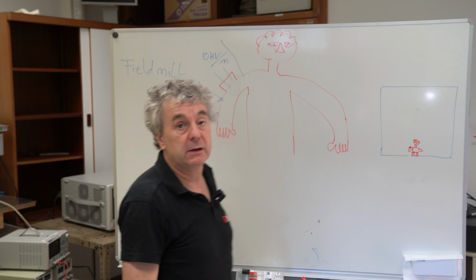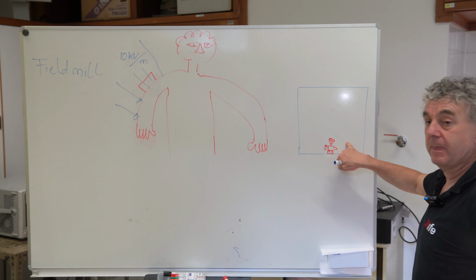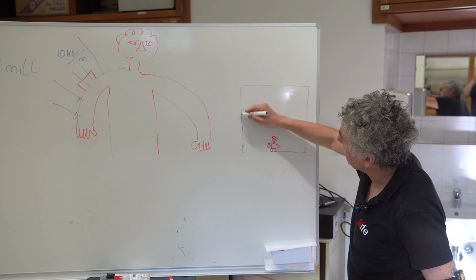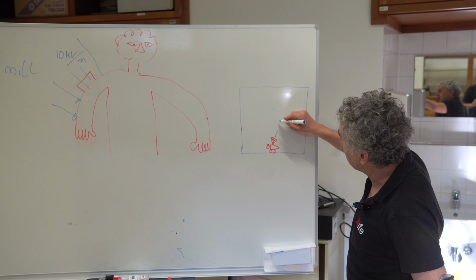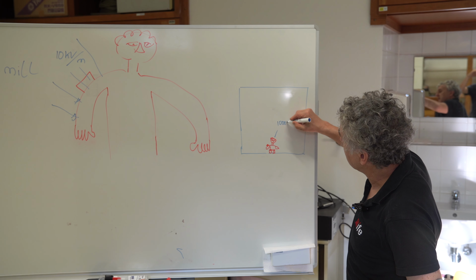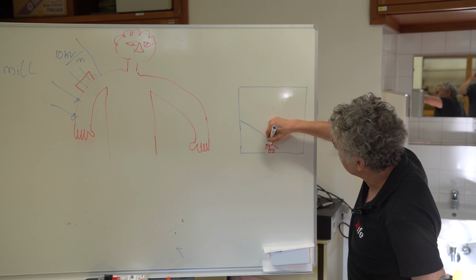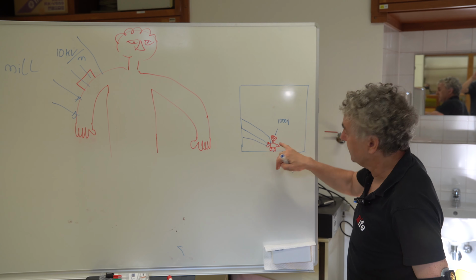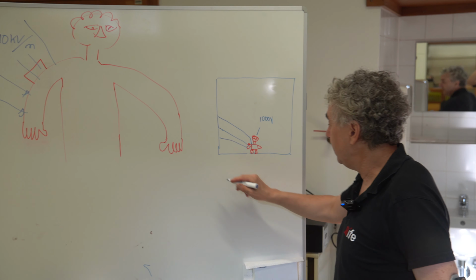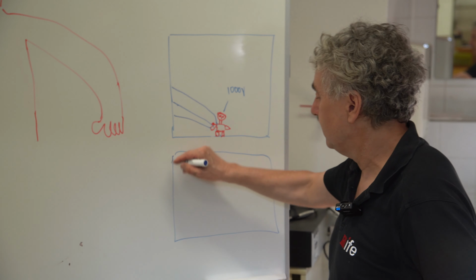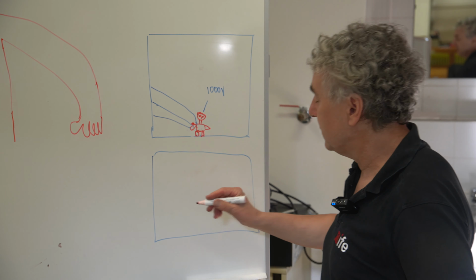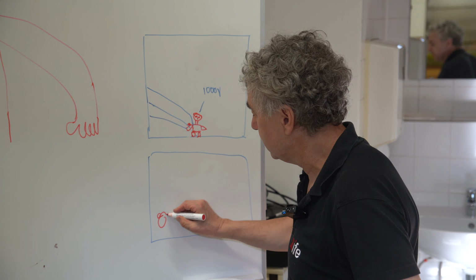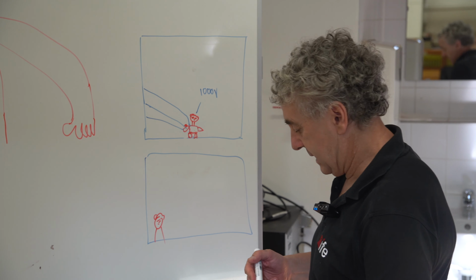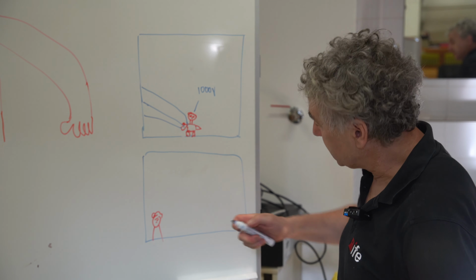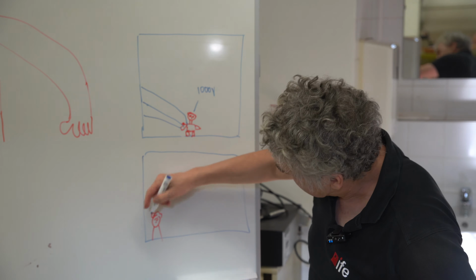The reason is the following: if we're in a big room, the metal wall is far away, so if I'm charged at 1000 volts, the field strength at the sensor is small. But if I'm standing close to the wall, the field strength is much higher. So the estimation of the voltage would be wrong.